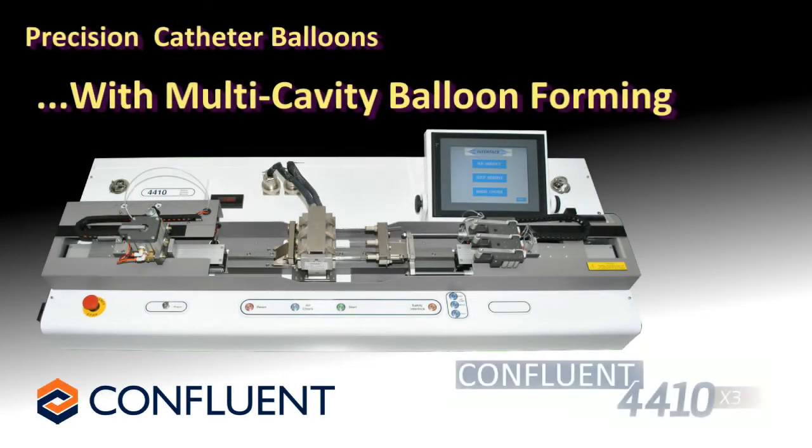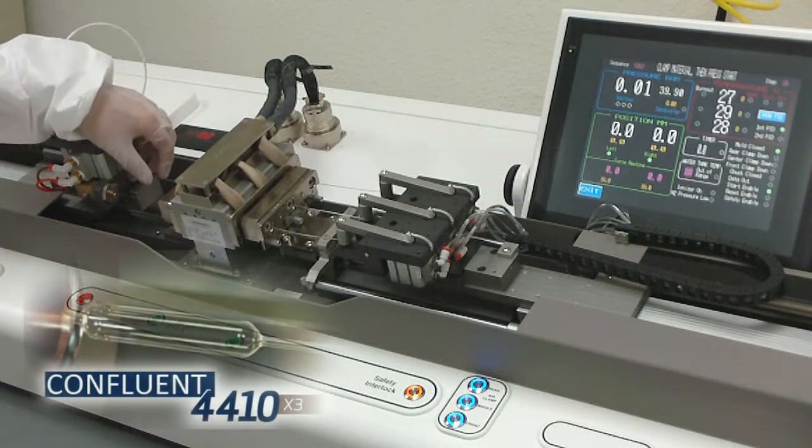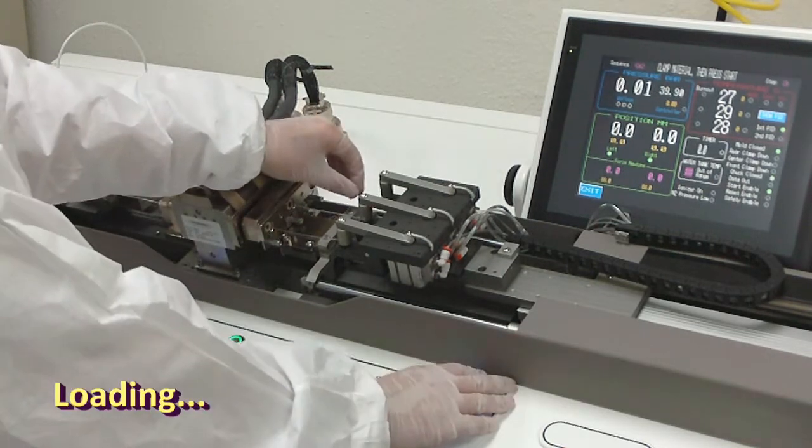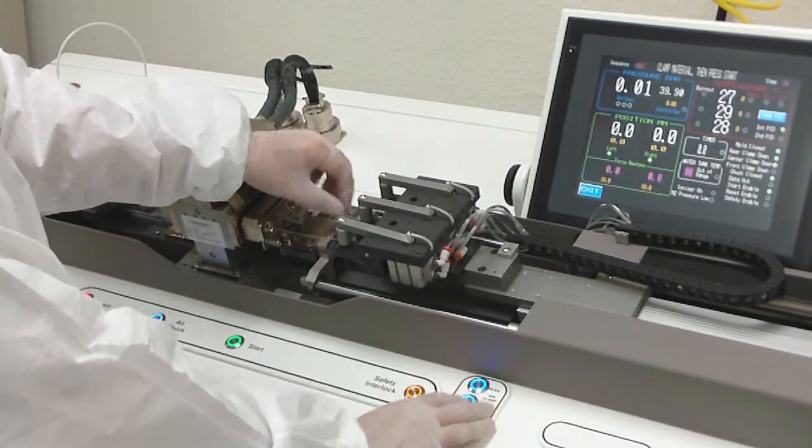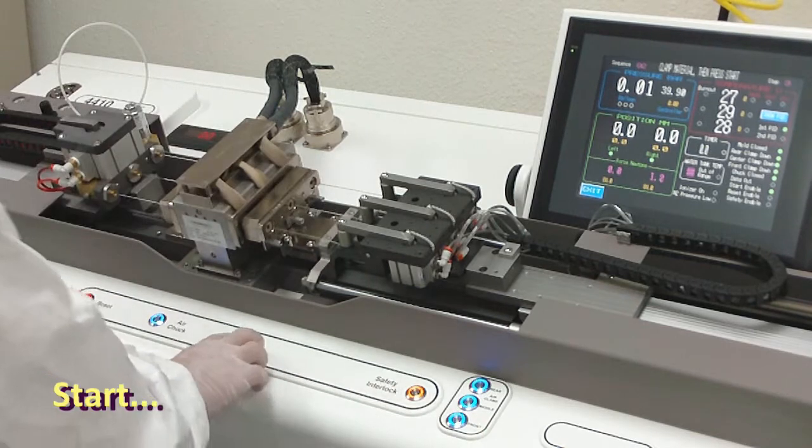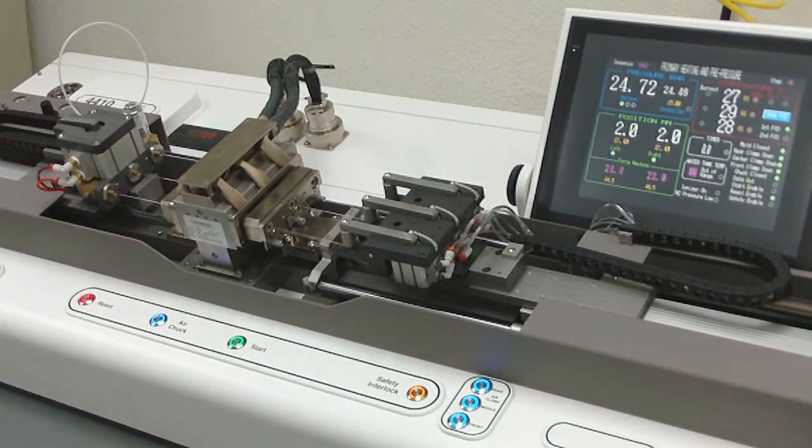Confluent Medical Technologies, a pioneer of computerized balloon forming, uses precision extruded balloon tubing in metal molds with precise heating and cooling, and exact calculated stretching and pressurization parameters. This time-proven process works very well for balloon production where small to medium quantities are needed.